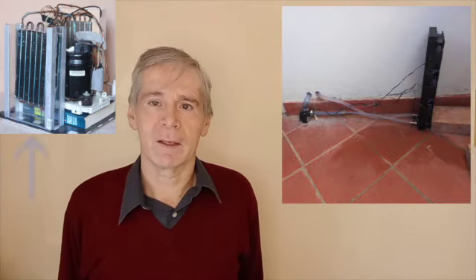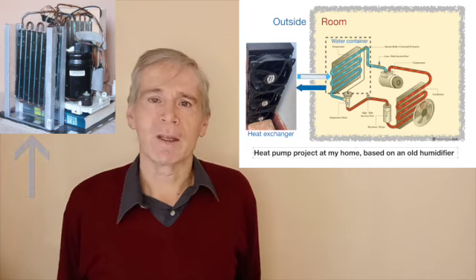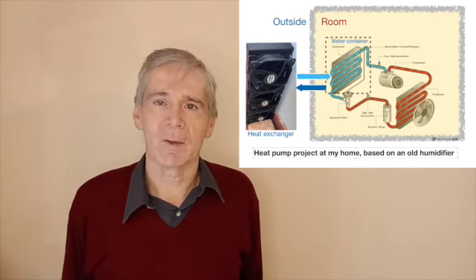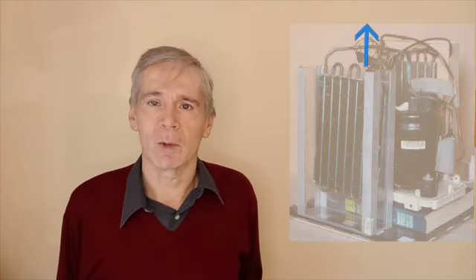Then it goes back through the wall into the house and into the bucket. Note that it enters the bucket on the other side of the heat exchanger compared to where the water exits the bucket. This creates a water flow across the heat exchanger and ensures it will not freeze.